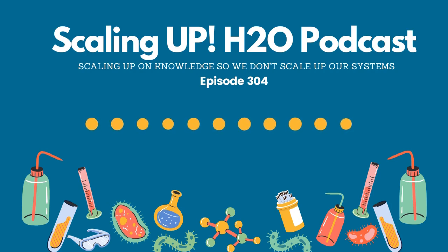So I'll tell you what, I'm going to go into one of the items on the acceptable, non-acceptable list, those standards that I was talking about. So let's talk about mild steel in an evaporative water type system. So anything less than 1 mil per year is considered excellent. Anything that's less than 3, but greater than 1, of course, would be considered very good. And that goes all the way up to anything that's greater than 10 mils per year is unacceptable. And there's a good range, a fair range, and a poor range in between that.